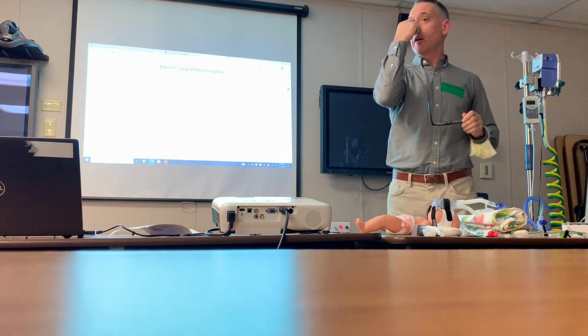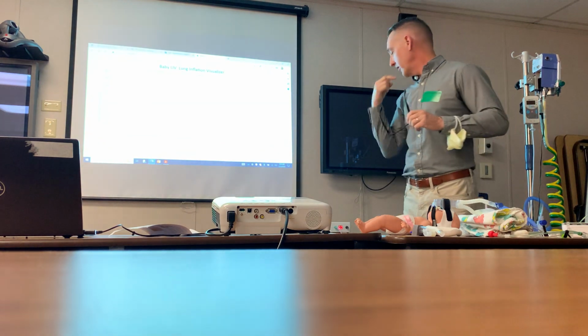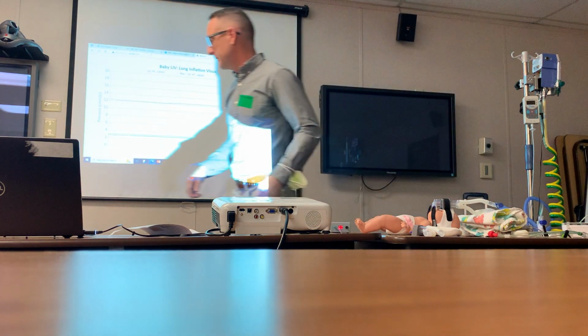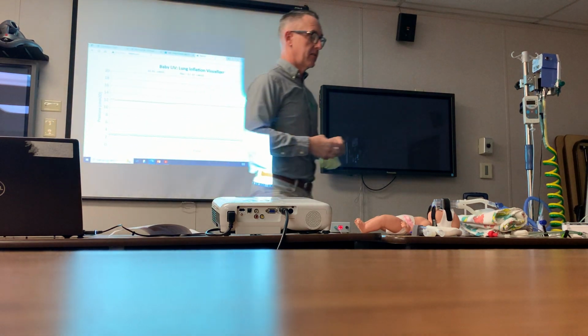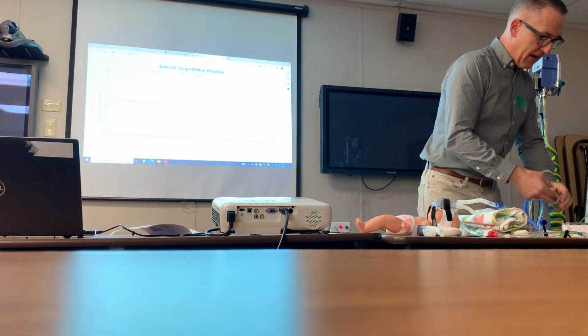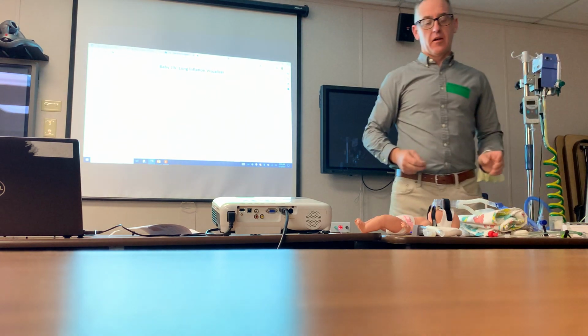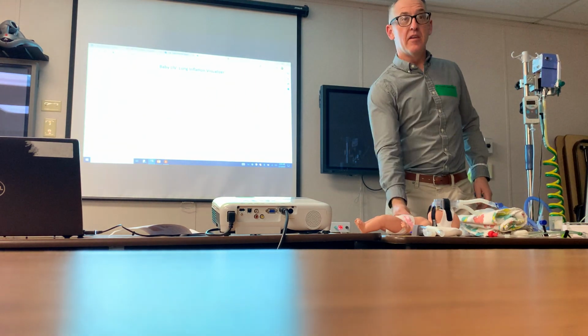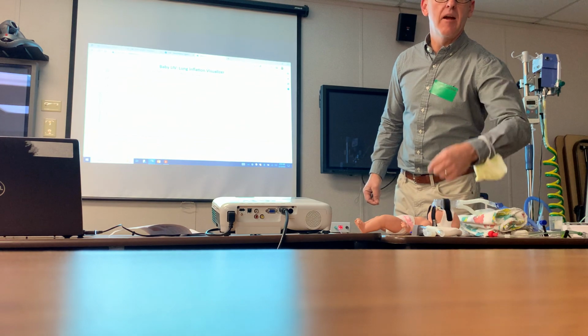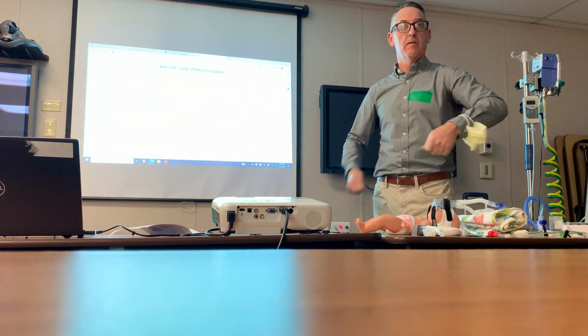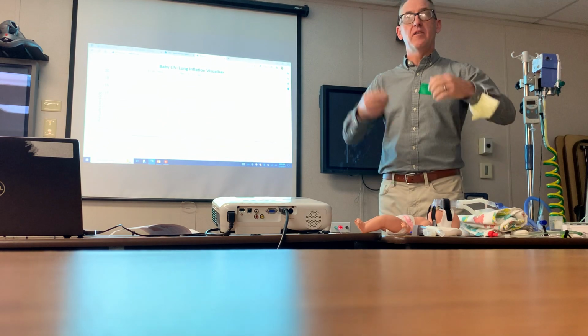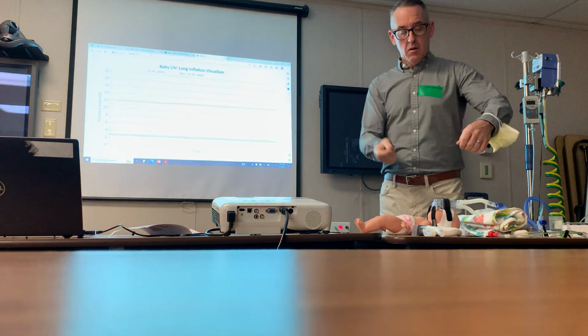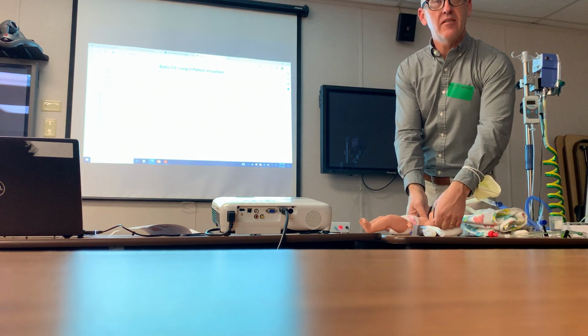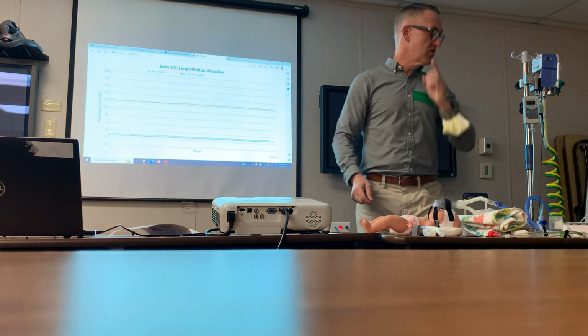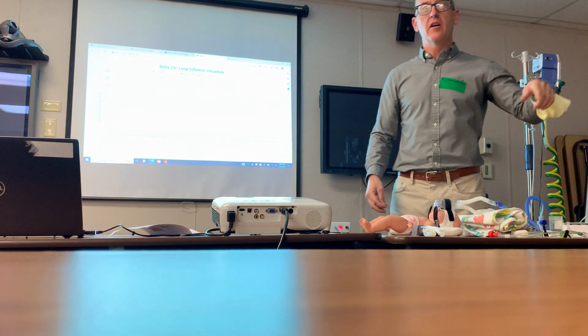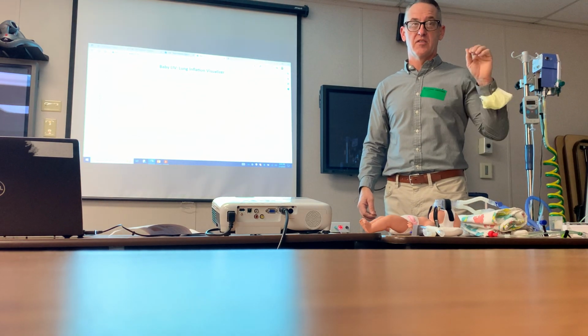What if you see a breakdown right here, a triangle right around the nose? What's causing that? The mask. And that is almost always caused by the RT taking a strap on this side and the RN taking the strap on this side, and there's this tug of war just to get that on, and they put it down and the mask is smashed down. Only one person should tighten this with the mask, making sure it's basically kissing the face just enough until it starts to bubble, or you get a reading on your ventilator that says everything is okay, and then stop.